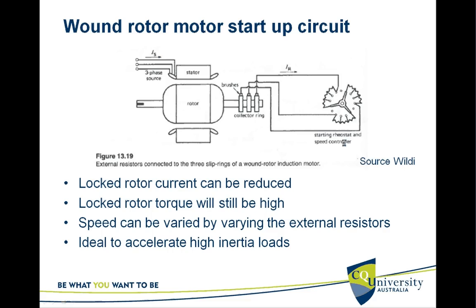You can change the speed by varying the external resistance — you just step it manually. This mechanism is ideal for accelerating high inertia loads, because you need high torque at the beginning. As the high inertia load gathers speed, you can reduce the torque little by little in steps.